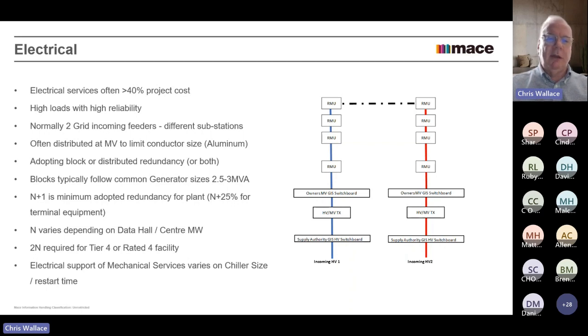Obviously, if you go 2N, you're rated for tier four, and that suddenly gets very, very expensive. And this is just generally the scheme that you'd use to support mechanical or electrical works. But really, how much and how well you support the mechanical systems is normally a function of the chiller size. Nearly always the blocks and the chillers you're using are going to be a bit big to start on a UPS unit, or the UPS is going to have to be quite a sizable UPS to restart a chiller.